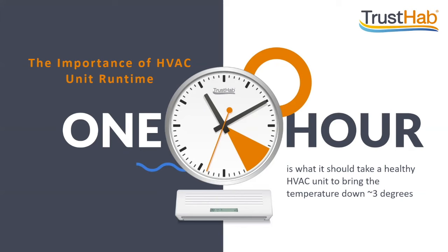So on this note, while there are many different signs that can point to a potential HVAC malfunction, one of the most telling is the specific amount of time a unit takes to cool. HVAC experts say an efficient, healthy unit should take around 1 hour to bring the temperature down 3 degrees. At minimum, a unit should run for 20 minutes an hour, or ideally 30.